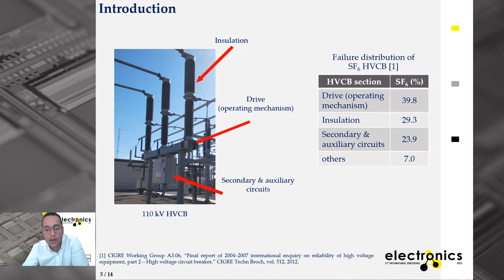The major failure modes for the high voltage circuit breaker can be divided into three categories. We can have mechanical failures, when the circuit breaker does not open or close on command, or it opens and closes without the command. We can have electrical failure modes, which are mainly related to making or breaking, or the resistance of the contacts of the high voltage circuit breaker varies and cannot carry the current. Or we have the insulation problem, which can be leakage of SF6 gas, or it can be external, such as breakdown across the poles of the circuit breaker.